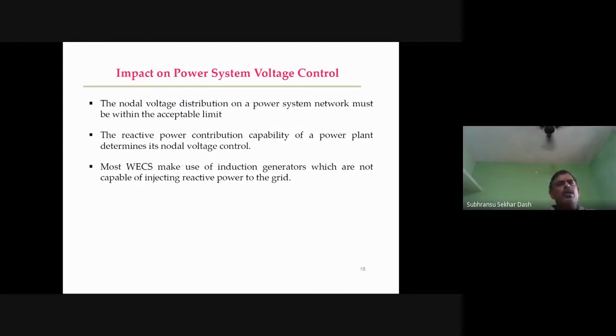Impact on power system voltage control. The nodal voltage distribution on the power system network must be within the acceptable limit. The reactive power contribution capability of a power plant determines its nodal voltage control. So what I am telling is, voltage control is very, very important. If you want to maintain system stability, you must be able to maintain the voltage properly. Nodal voltage should be properly maintained, because you know that most of the wind energy conversion systems make use of induction generators, which are not capable of injecting reactive power to the grid. So it is very, very important.